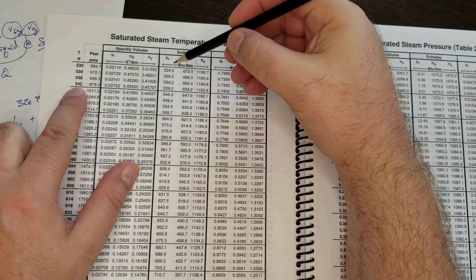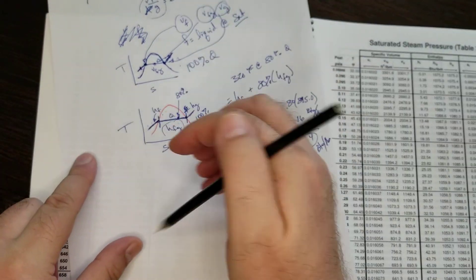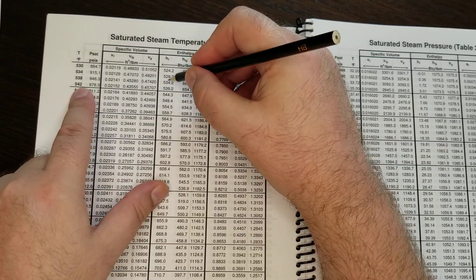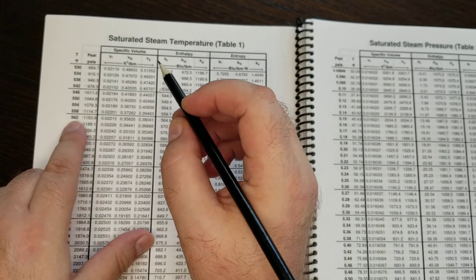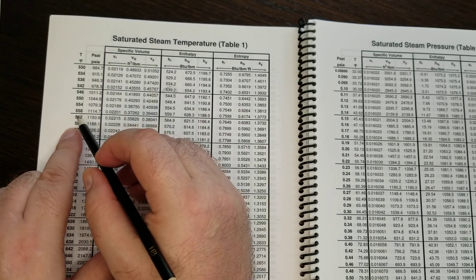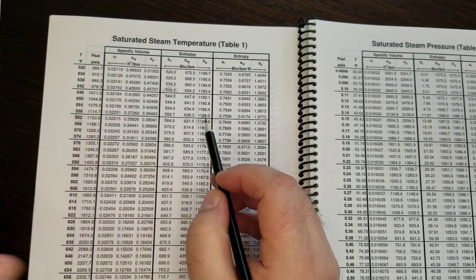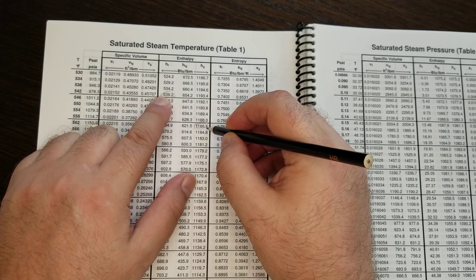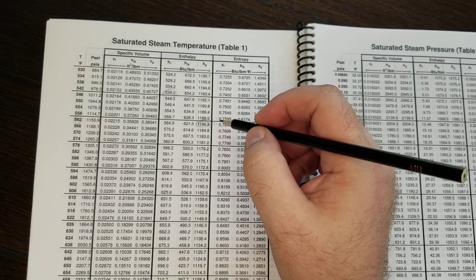And I've seen some of you use temperatures like the turbine work problem where I give you 542 degrees Fahrenheit as a saturated liquid, right, as a reactor coolant going in, which means you're down here. So for 542 degrees Fahrenheit, you would be using this value, 539.2 BTUs per pound mass. But for the steam, when I say saturated steam, that means steam, dry steam, steam at 100% quality. This coffee is not kicked in yet. So 562 degrees Fahrenheit, I'm giving you this point here, which is this value. So it's the difference between these two numbers multiplied by the mass flow rate is how you solve that steam turbine problem.